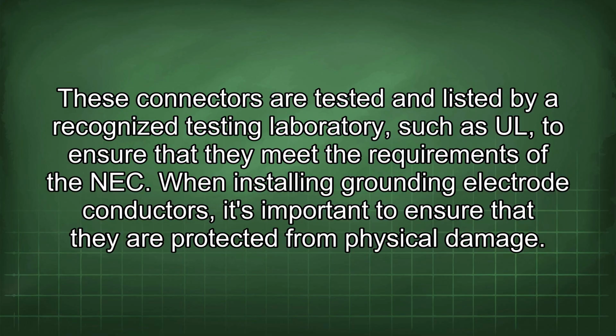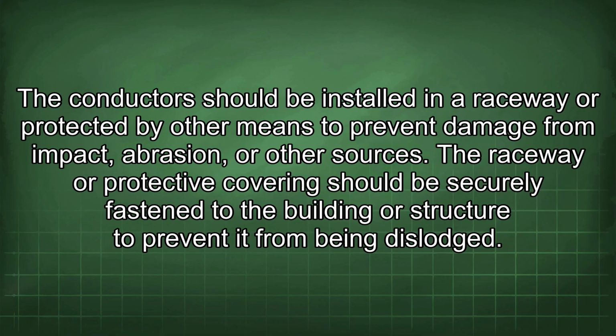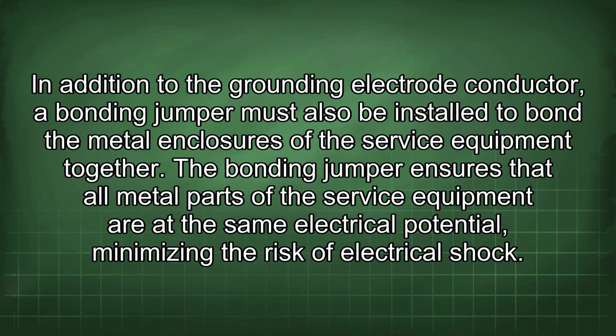When installing grounding electrode conductors, it's important to ensure that they are protected from physical damage. The conductors should be installed in a raceway or protected by other means to prevent damage from impact, abrasion, or other sources. The raceway or protective covering should be securely fastened to the building or structure to prevent it from being dislodged. In addition to the grounding electrode conductor, a bonding jumper must also be installed to bond the metal enclosures of the service equipment together.